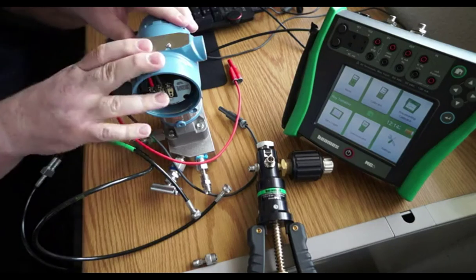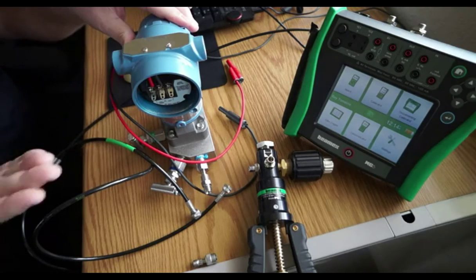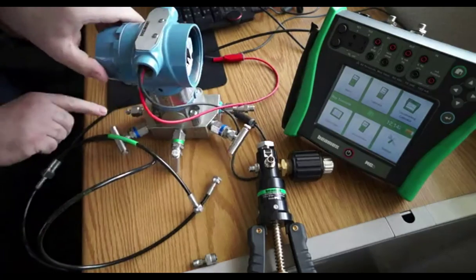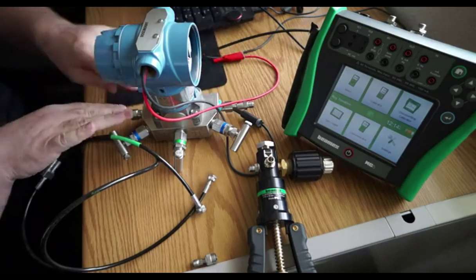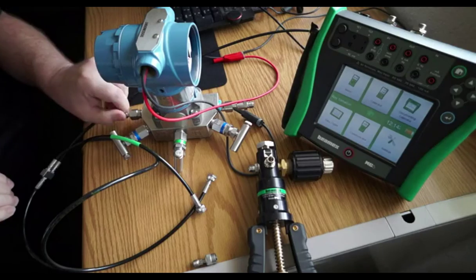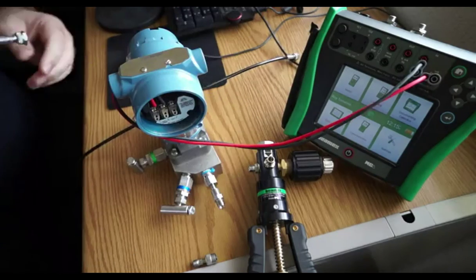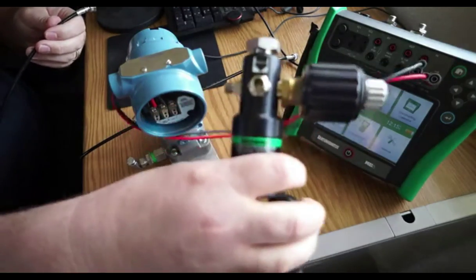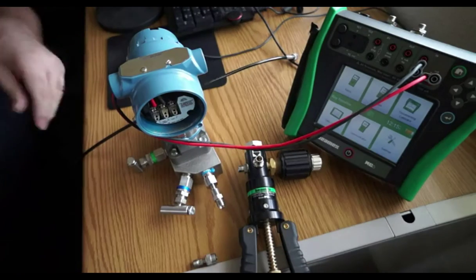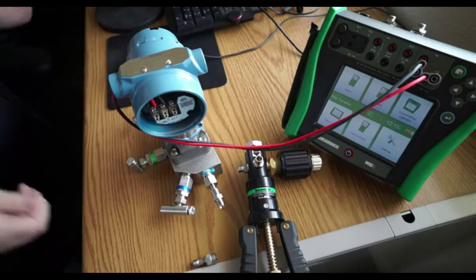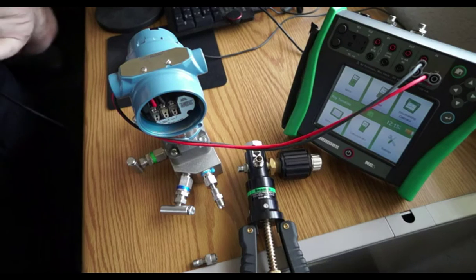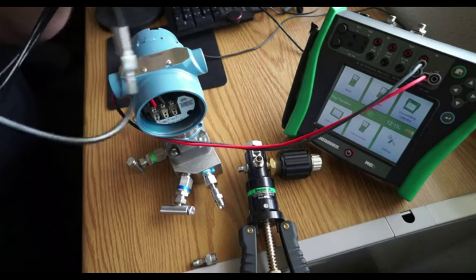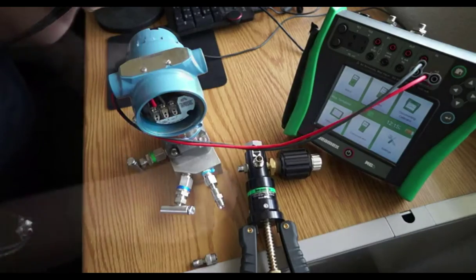Welcome to today's calibration talk. We'll be calibrating a pressure transmitter. What do we got? Well, we have a Rosemount 3051C differential pressure transmitter. We have a high side over here, a low side over here. The low side, I have the vent opened. Pressure-wise, we've got a pressure pump. Our pressure hose itself has 3 legs on it, so we have 3 of these, and then there's a union in the middle holding everything together.